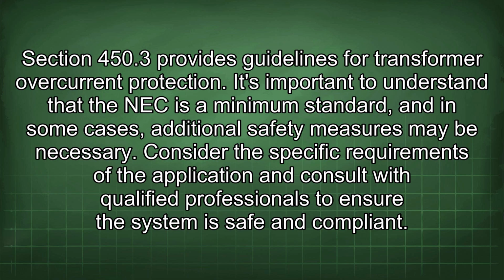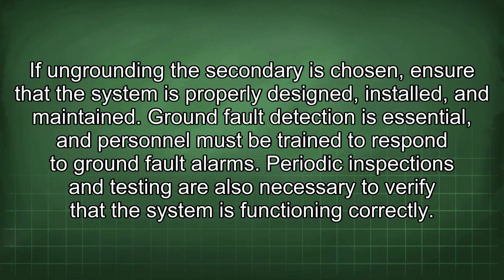It's important to understand that the NEC is a minimum standard, and in some cases, additional safety measures may be necessary. Consider the specific requirements of the application and consult with qualified professionals to ensure the system is safe and compliant. If ungrounding the secondary is chosen, ensure that the system is properly designed, installed, and maintained. Ground fault detection is essential, and personnel must be trained to respond to ground fault alarms. Periodic inspections and testing are also necessary to verify that the system is functioning correctly.